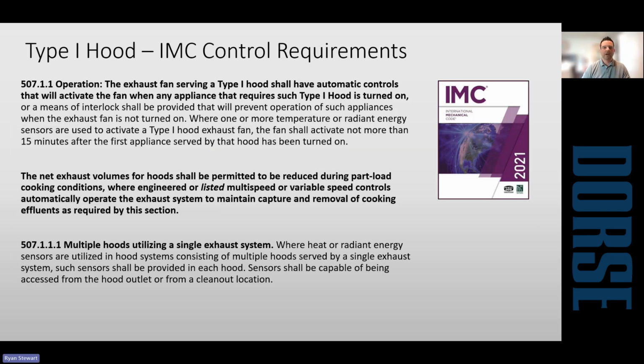This is just the section out of the IMC that talks about that in more detail. When you have multiple hoods on a single fan, each of the hoods is going to need a heat sensor. And if there's heat under any one of those hoods, the system needs to turn on within 15 minutes.